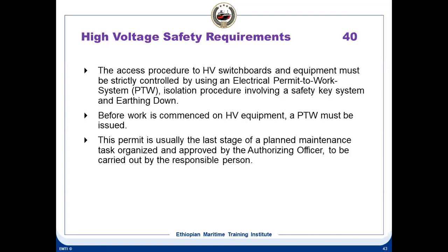And before the work is commenced on HV equipment, a PTW must be issued. The permit to work is issued by the chief engineer. After he is satisfied that all the precautions have been taken and all the isolations have been done, then he gives a permit to work. So you need to have approval from the company also when you work on high voltage equipment. The permit is usually the last stage of a planned maintenance task, organized and approved by the authorizing officer to be carried out by the responsible person.